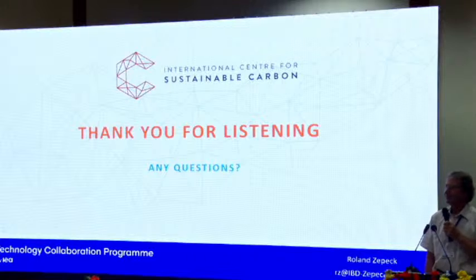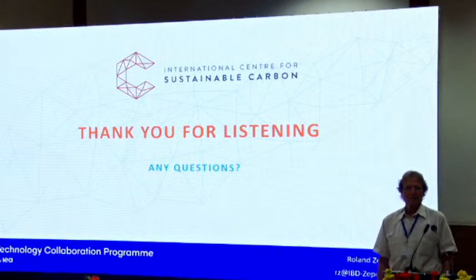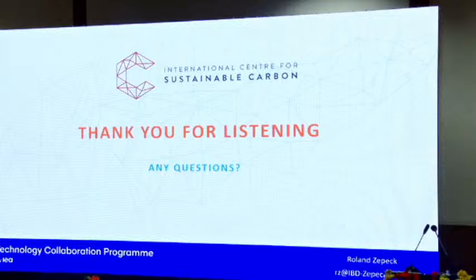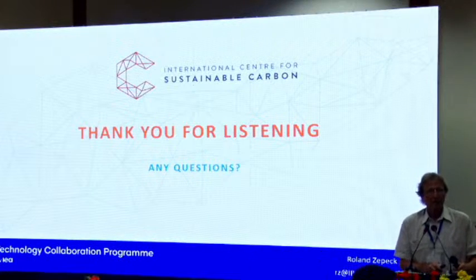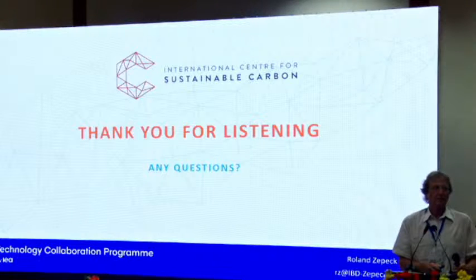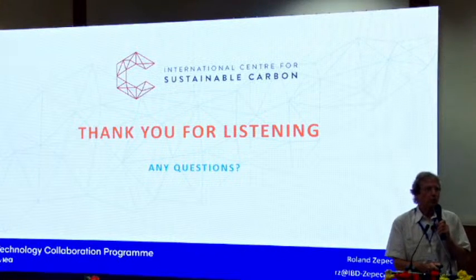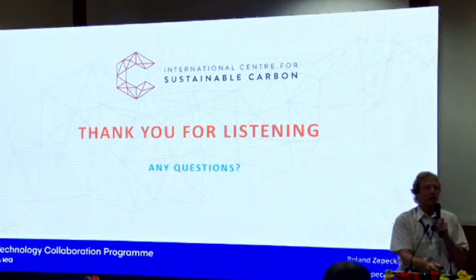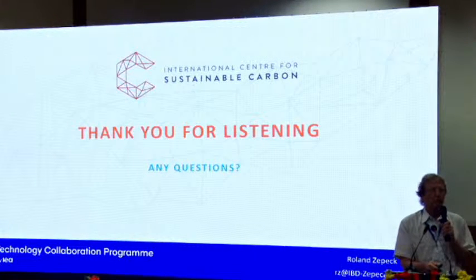Any questions? Sir, we have a stack of 275 meters, and my analyzer sensor is at 43 meters. Where is the ideal location for the analyzers to be kept? My sensor is at 43 meters, and the analyzer is ideally at 0 meter. Do you have a platform? Yes, we have a platform at that. A sizable platform.